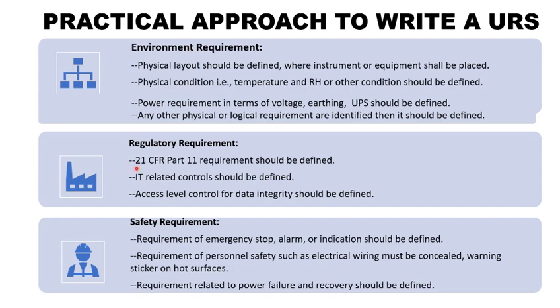Next is regulatory requirements. 21 CFR Part 11 requirements related to electronic records and electronic signatures should be defined. IT-related controls such as copy, paste, delete, move, etc. should be defined to control data integrity. Access level controls should also be defined to ensure unauthorized users cannot access the system.